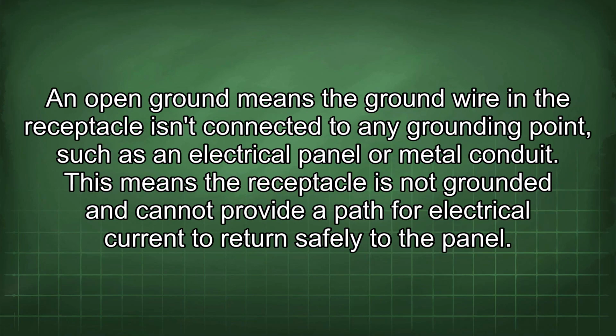An open ground means the ground wire in the receptacle isn't connected to any grounding point, such as an electrical panel or metal conduit. This means the receptacle is not grounded and cannot provide a path for electrical current to return safely to the panel.